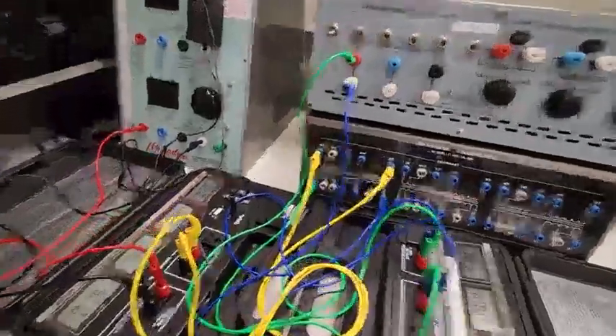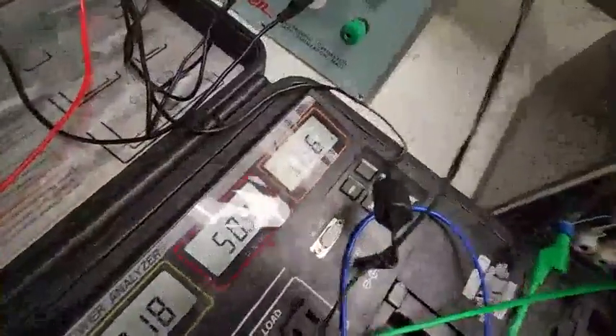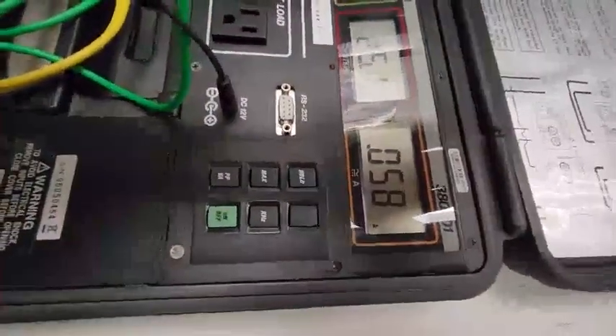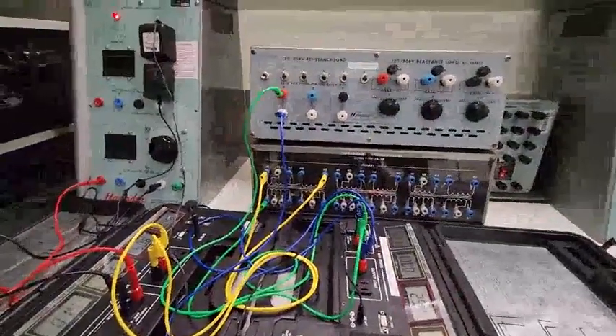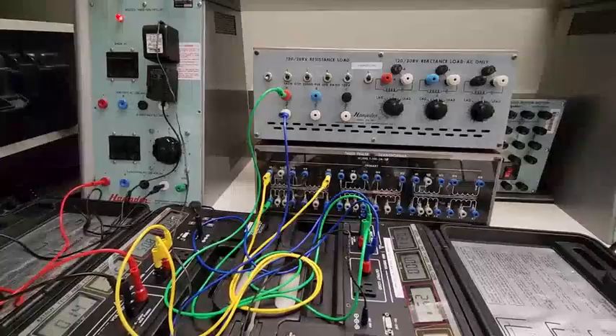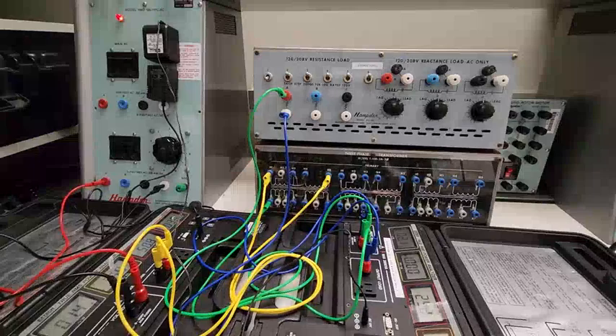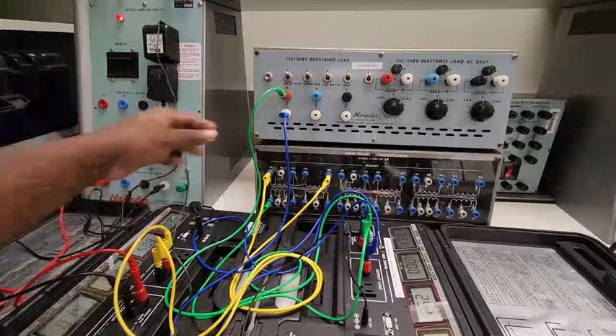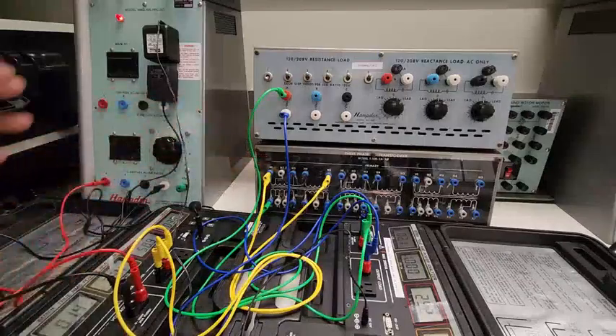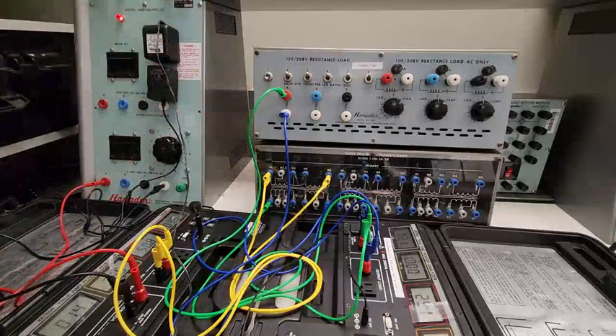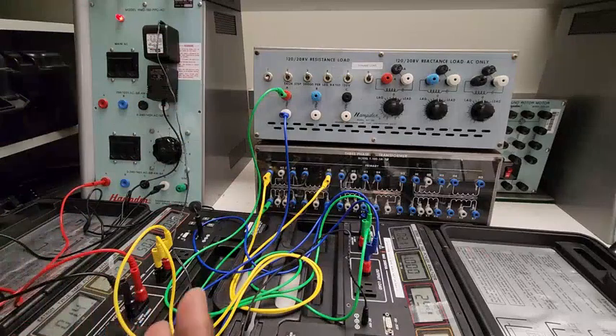If you look at the current, the input side's current is 0.036 and the output side's current is 0.058, approximately doubled. It's not exactly double because there are some losses in the system: losses in the cable, losses in the transformer's winding, losses in the resistive load, and also some losses in the transformer core.